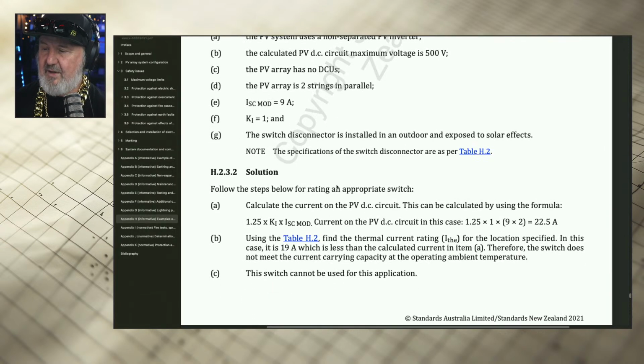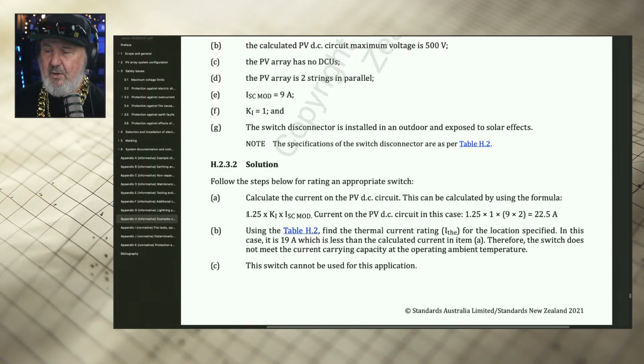So we run through the equations now. There's that same equation before, 1.25 times K, K being bifaciality, is 1 because it's not bifacial, but we've now got two strings. So that 9 amps is times 2, which means we're up to 22.5 amps of potential fault current. And using table H2, we find the thermal current rating for the location, in this case, is only 19 amps, remember? If I go back up to table 4.2, you'll see it's only 19 amps. So therefore, this switch does not meet the current carrying capability at the operating ambient temperature. So this switch cannot be used.